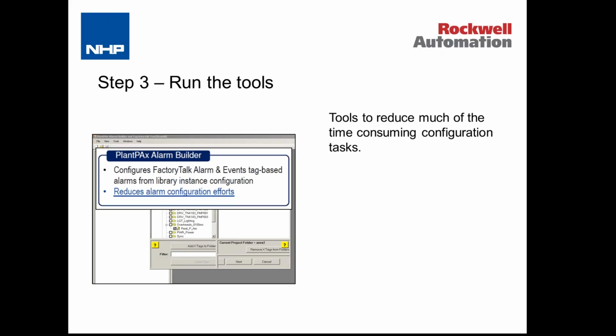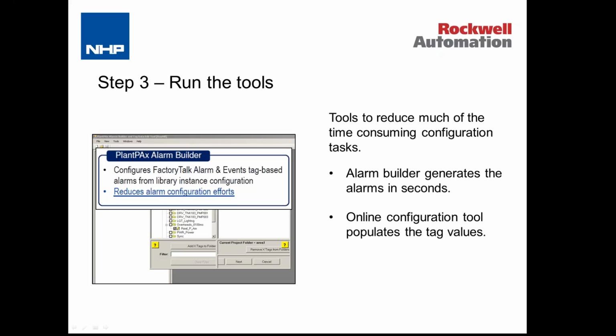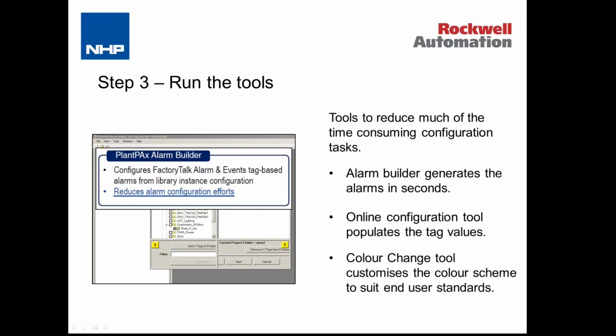And the Alarm Builder can literally save you hours and hours of work. Using the Alarm Builder, we can build hundreds, even thousands of alarms in a matter of minutes rather than in the many hours it would take to do that manually. There's also an online configuration tool that allows us to populate the configuration of the objects. Now, I mentioned that we can do the configuration from the screen, which we can, and which is great for making little changes, or if you've only got a small number of objects. But if we've got a larger project where we've got hundreds of objects, although we can do it from the screen, it's probably more efficient for us to do it with this online configuration tool.